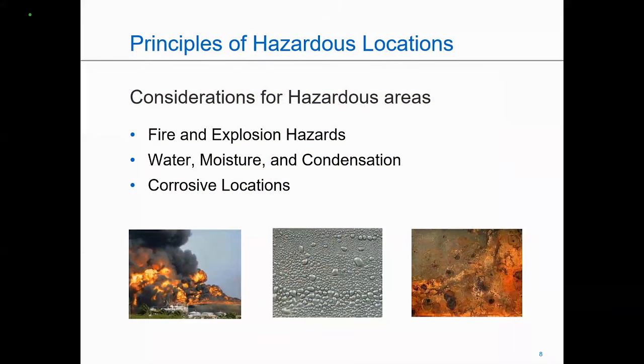So do I need to have a drain seal to allow that moisture to escape so I don't have an issue with my conductors getting damaged? And then condensation that can form inside enclosures. Those enclosures may have a breather and drain in them. And then, of course, anytime we have hazardous location areas, more times than not, it's going to be a corrosive condition.